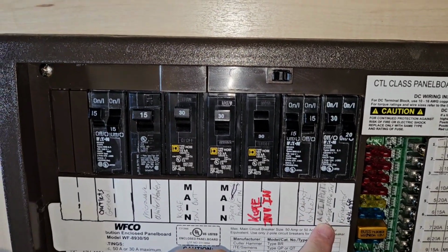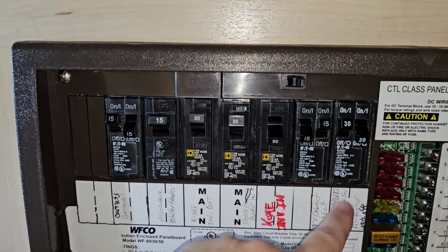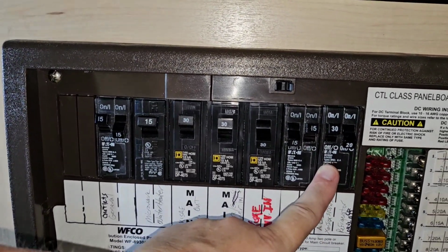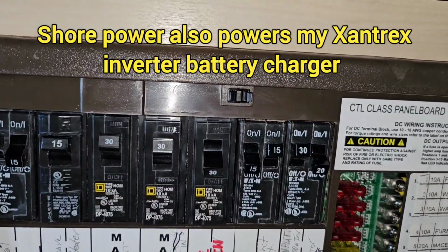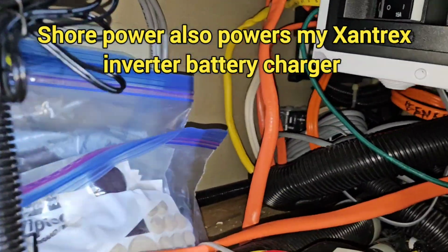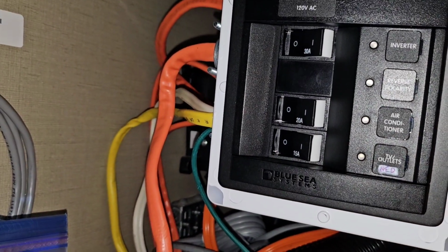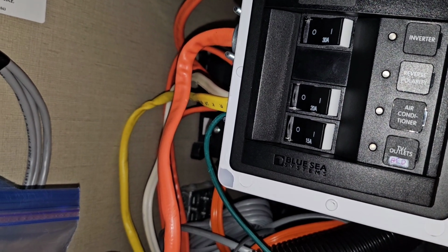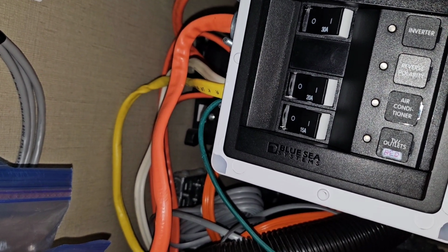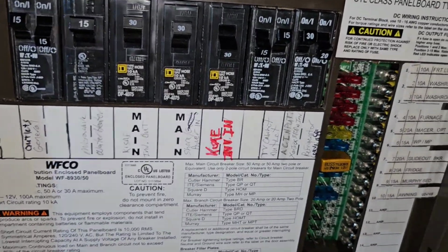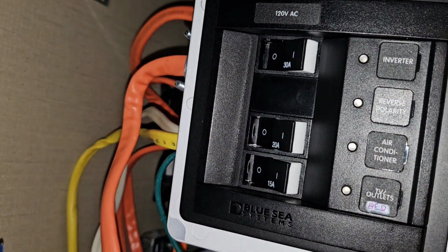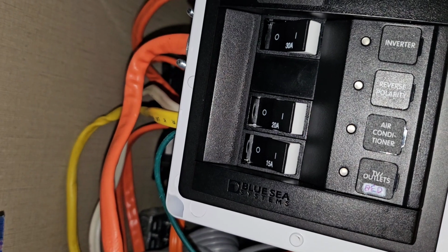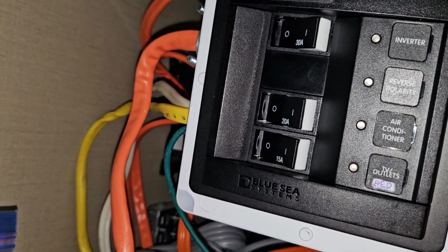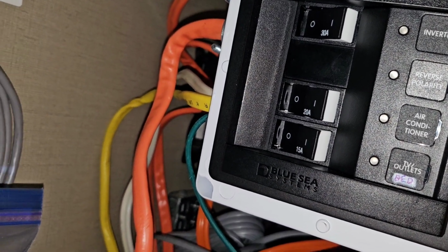Then my Xantrex 3000w inverter, this is its AC input. It picks up power from this bus and passes it through to the output of the Xantrex inverter, which connects here with a 30 amp breaker on the output, feeding two circuits: the air conditioner and my TV and bed outlets. So when I'm not using shore power, the Xantrex inverter strictly powers these circuits through that 30 amp breaker as the inverter output. It runs through this panel either on shore power or on batteries.